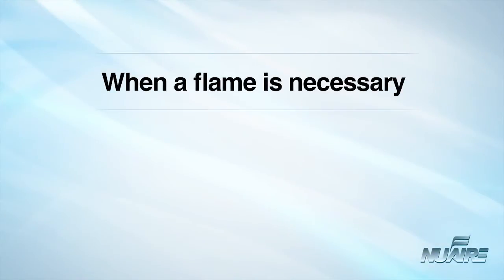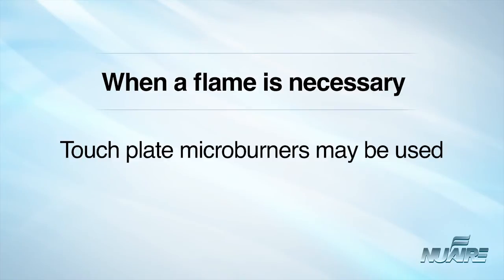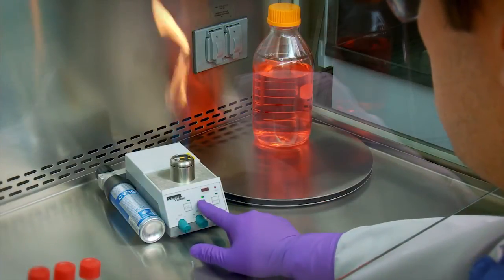When deemed absolutely necessary, touch-plate micro-burners equipped with a pilot light to provide a flame may be used. This will minimize internal cabinet air disturbance and heat build-up. The burner must be turned off when work is completed.